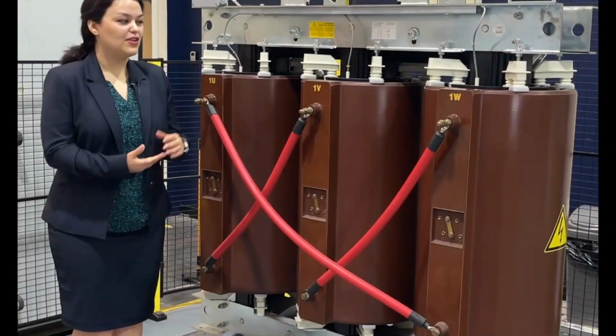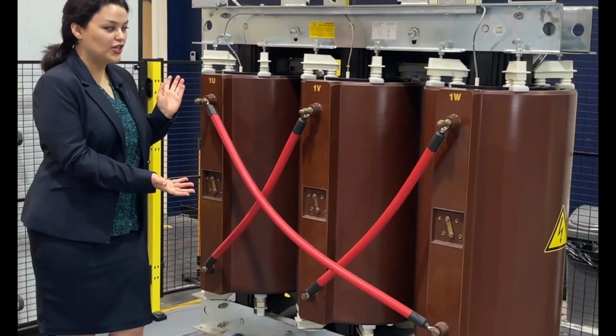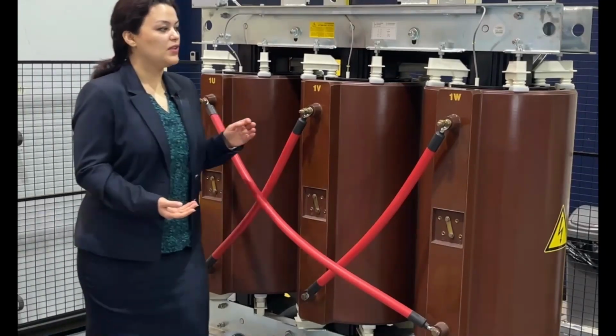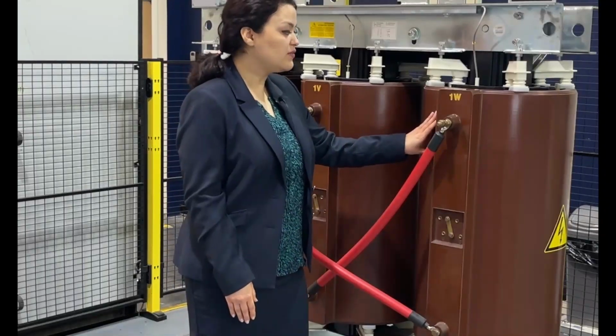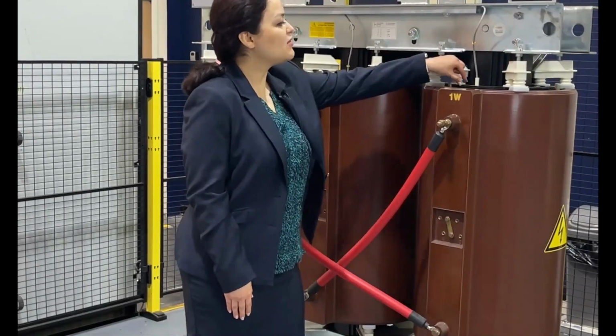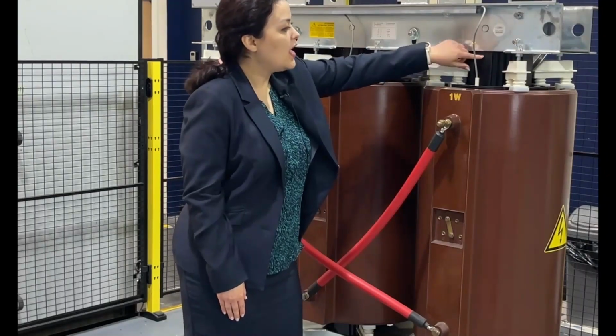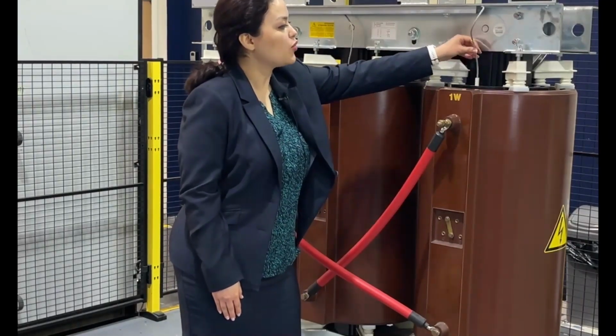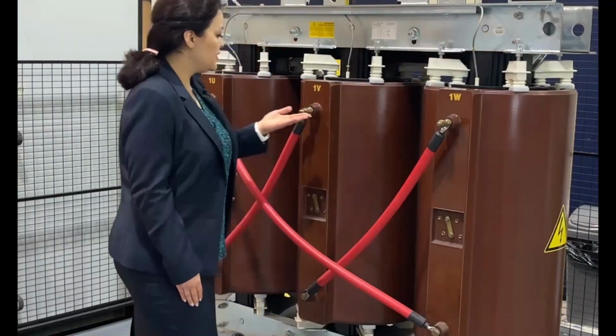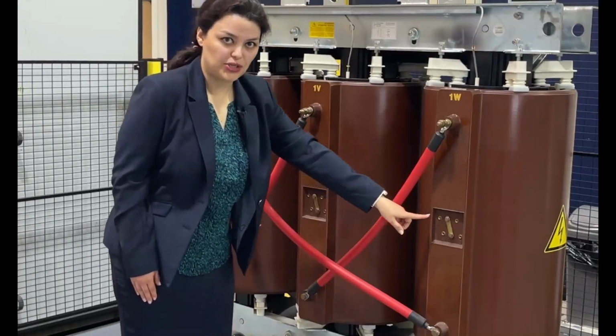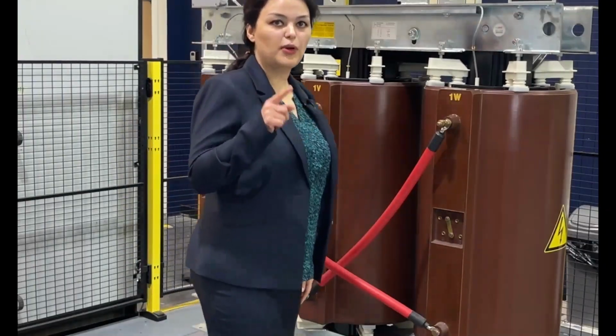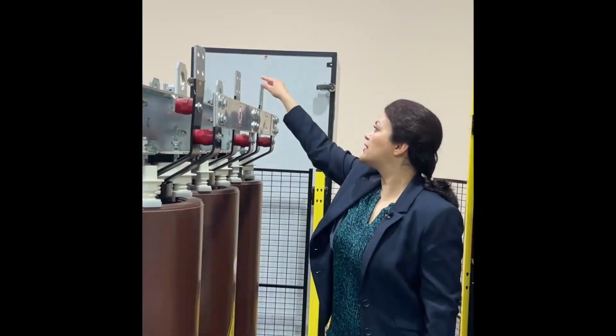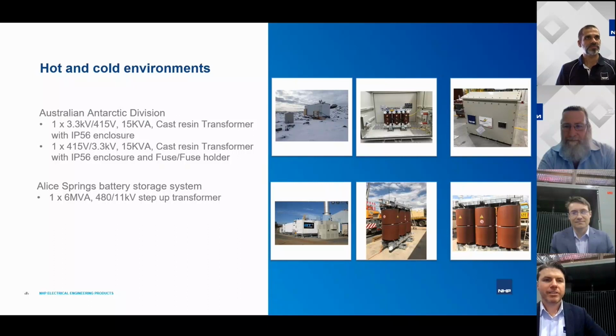Thanks, Nick. Here we are going to talk about the physical construction of a cast resin transformer. What we have here is an HV winding, which is cast in resin monoblock. That's the LV winding, and that's the magnetic core. Here we have temperature monitoring probes in the LV winding. These are the HV terminals, and this is the off-load tap changer. If you come to the other side of the transformer, I'm going to show you the LV terminals. These are the LV terminals, and this is the welded lifting point for the cast resin transformer. Back to you, Nick.